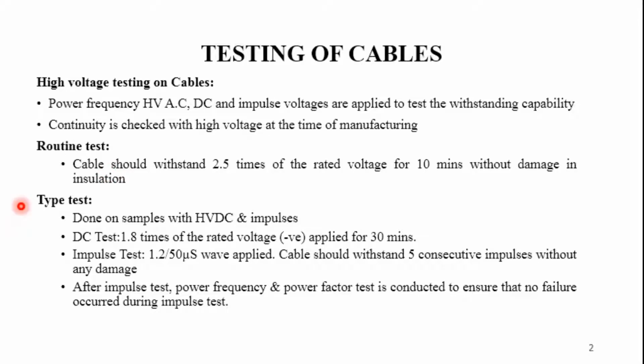Then the type tests are done on samples with HVDC and impulse voltages. The DC test consists of applying 1.8 times the rated DC voltage of negative polarity, which is applied for 30 minutes. Otherwise the cable is said to be unfit. So if it withstands the test, then for the impulse voltage test, generally we consider a 1.2/50 microsecond wave.